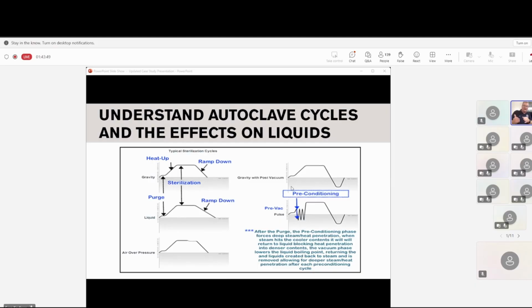And then what happens is it gets pulled down the drain, and now it preconditions the autoclave chamber back to a totally gaseous state again. So there's no liquids or anything in it. And now it's going to keep driving back up. And that's what it does. It puts the steam in, and it just keeps closing that down and pulling that liquid out until there's no spot left.